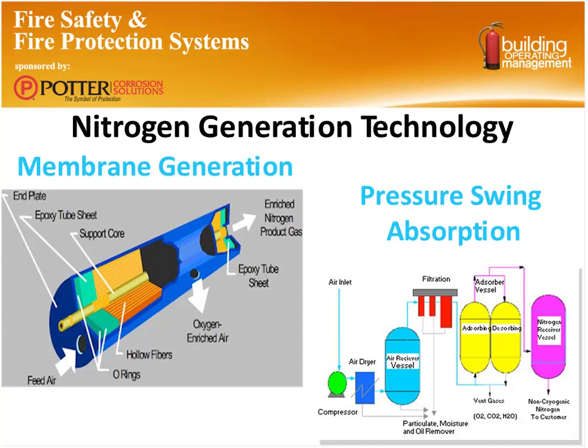So what the industry has done is come up with systems that actually strip nitrogen from the normal compressed air stream. There's two technologies that have been used to generate nitrogen. Some of them you've even seen potentially when you go get a set of tires today. They'll offer to fill your tires with nitrogen for quite a hefty fee in some cases, depending on your tire shop. But what they're using is a very similar technology, just on a very small basis. That's the typical membrane generation style, where you put compressed air through a filter, and due to the differences in the molecular size of those oxygen and nitrogen molecules, you can actually separate the oxygen from the nitrogen and put that into some kind of a receiver to use in your sprinkler system or to fill tires.